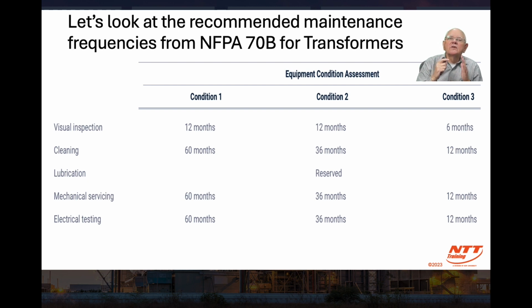If my equipment falls into condition number 1, I have to do visual inspections every 12 months. Same for condition 2. If it's condition 3, because this transformer falls under equipment condition 3, I've got to do visual inspection every 6 months. This is right out of 70B.